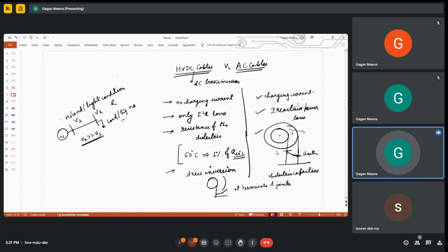Because of this, DC cables have very high current and voltage ratings. They can have lesser insulation thickness and are compact. DC cables are always single core and stranded. They may have plastic or impregnated paper insulation, and oil and gas filled DC cables have been used for more than around 100 kilometers.